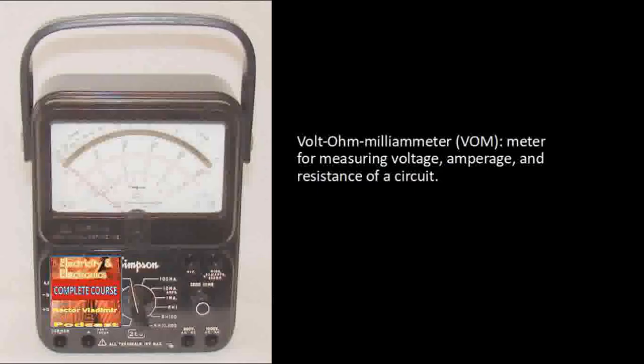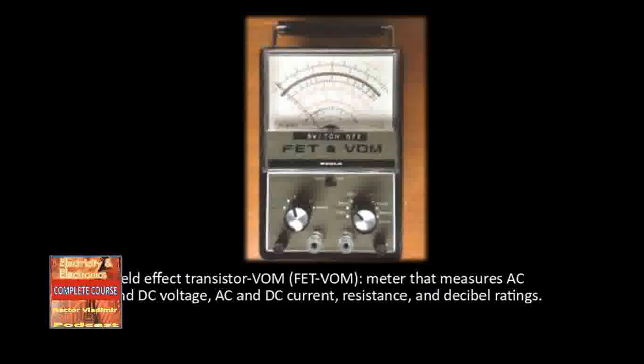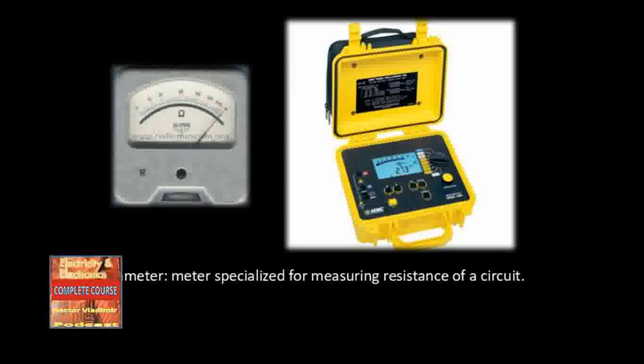Section 2.5: The volt-ohm-milliammeter, or VOM, is a common multimeter that combines a voltmeter, ammeter, and ohmmeter in one instrument. The VOM is inexpensive and portable, but may have low input resistance in ohms per volt on the lowest voltage range, causing accuracy problems. When the field effect transistor was developed, the FETVOM was designed to overcome the low input impedance problem, measuring AC and DC voltages, AC and DC current, resistance, and decibel ratings. Some multimeters are also equipped with accessories such as temperature probes.